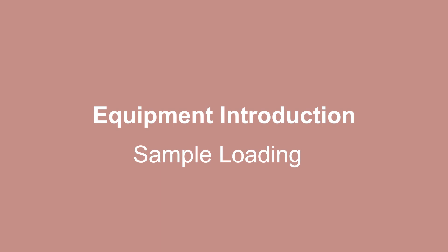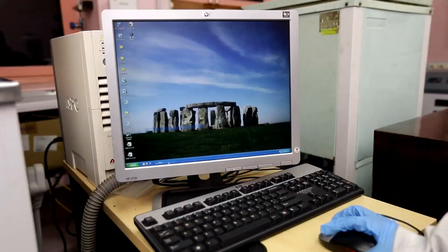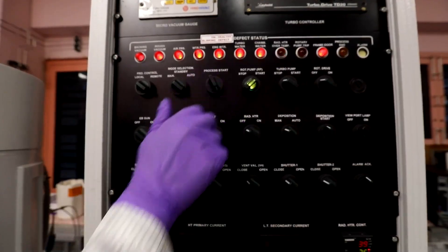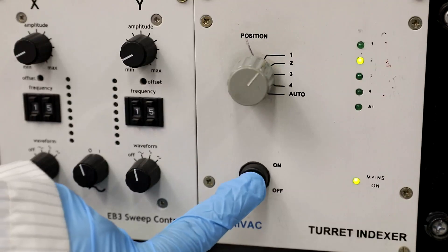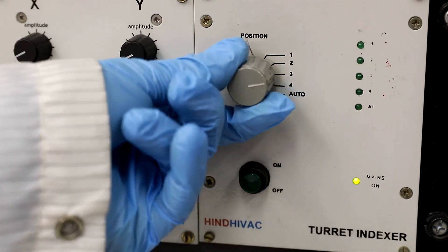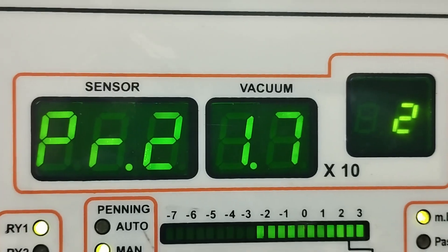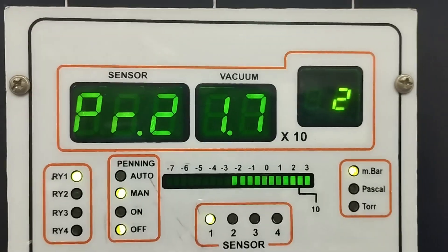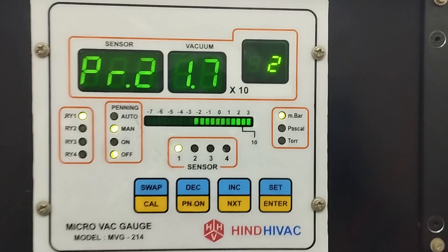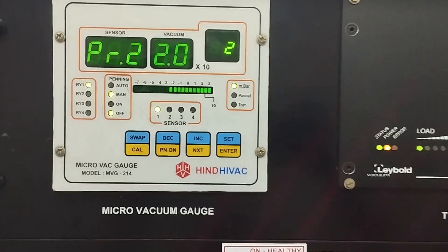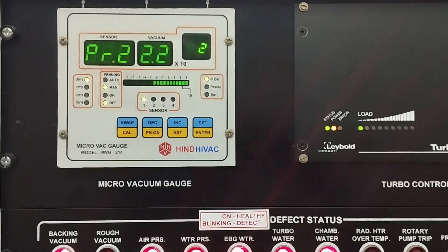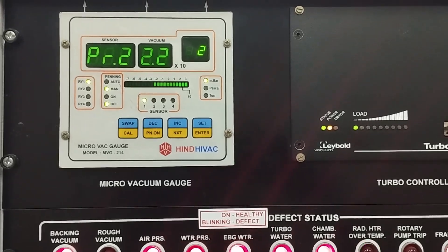Equipment introduction and sample loading. Switch on the system and vent the chamber for sample loading. When the chamber pressure reads 1000 mbar atmospheric pressure, we can open the chamber to load the sample inside the chamber.